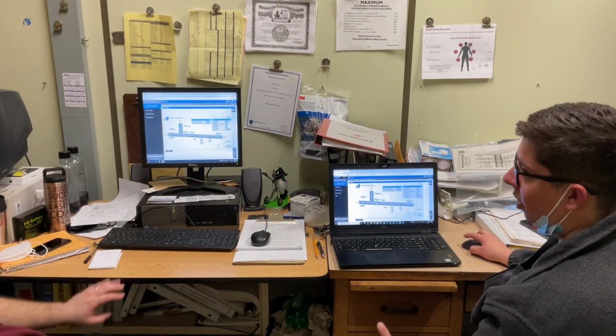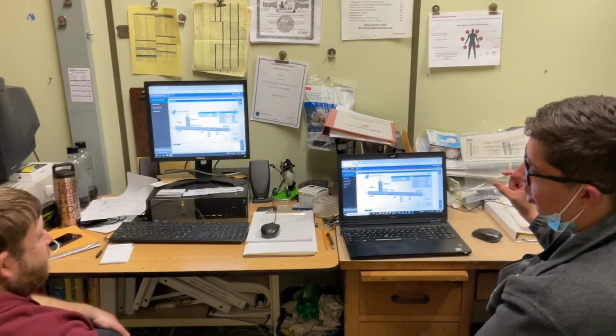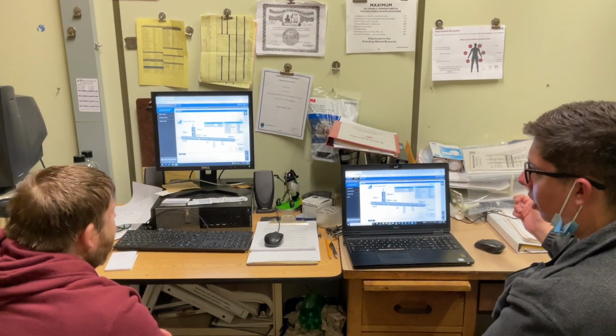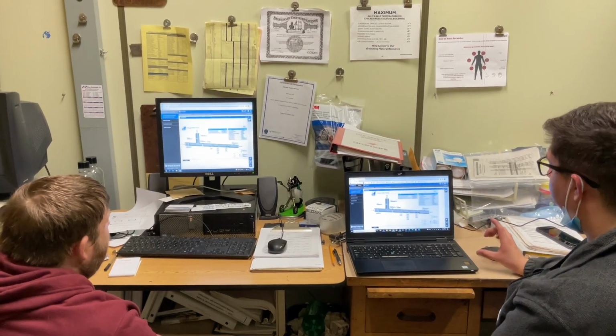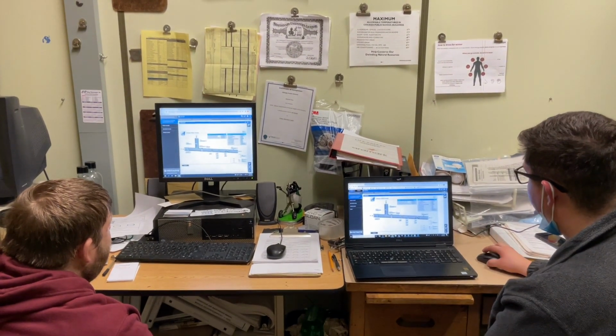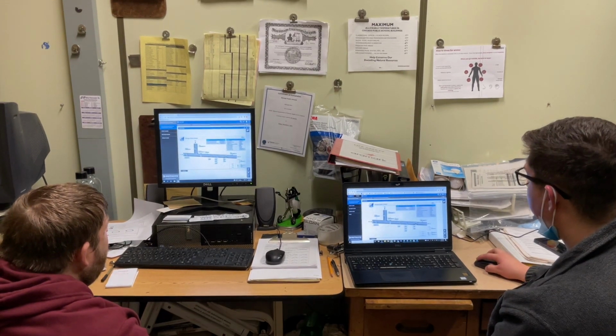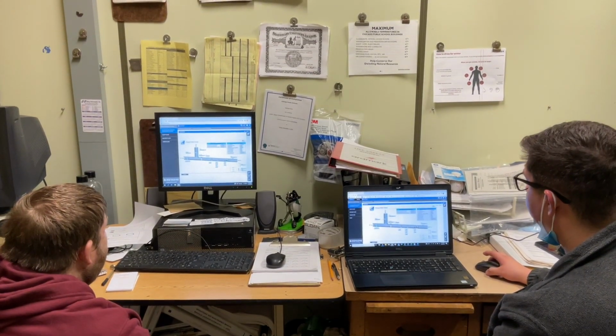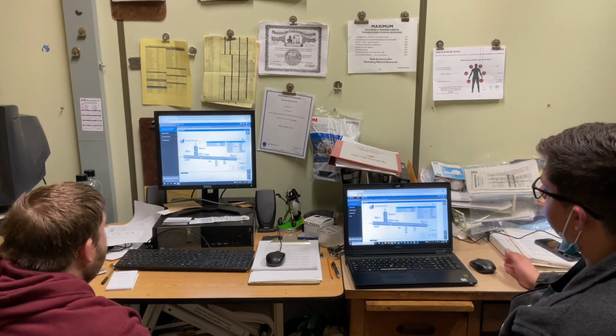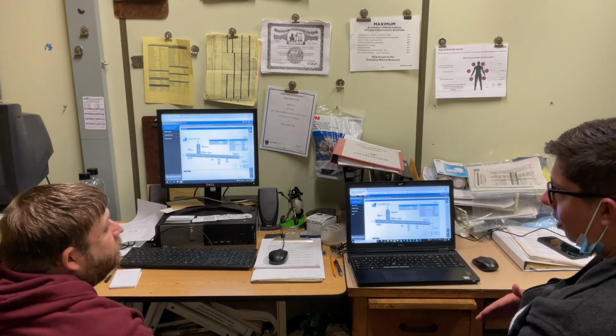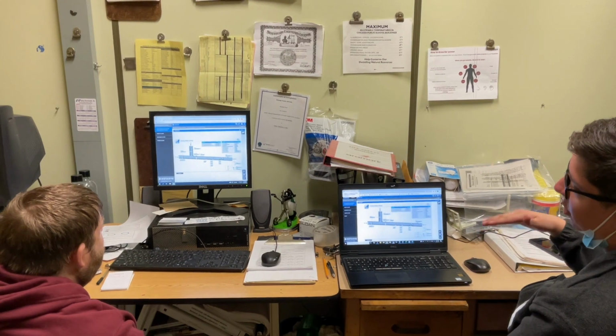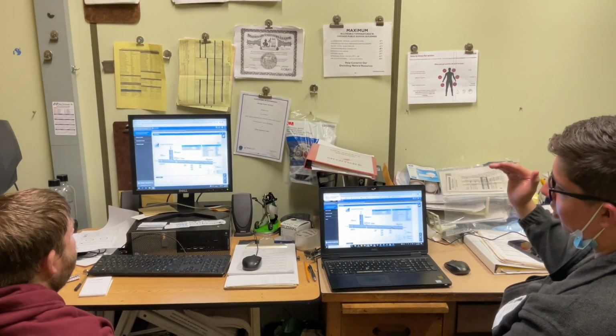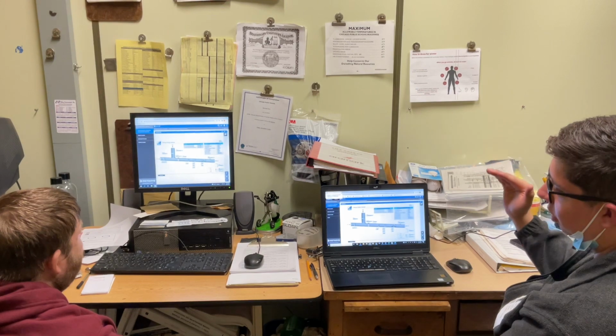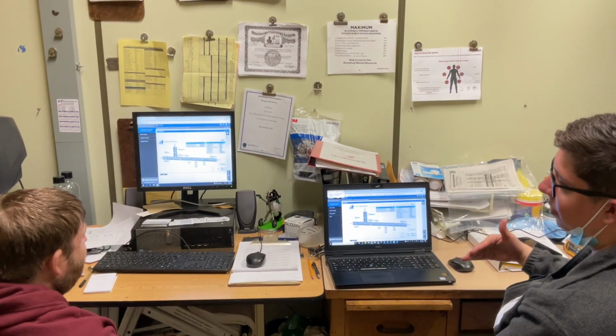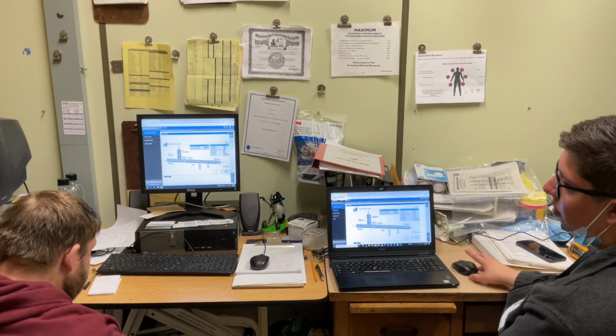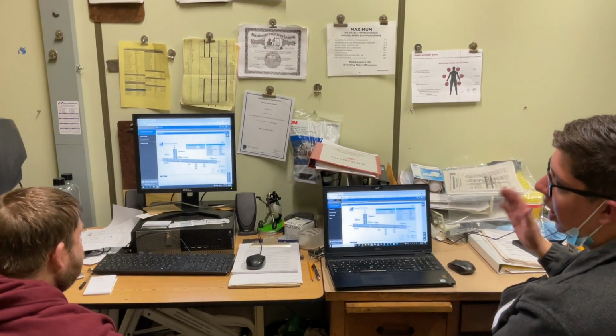Yeah. So you just set your set point. You're going to have plus or minus 2 degrees for your effective heating and cooling set points, and that's actually what it's controlling for. So at 76 on your set point, that makes your effective cooling set point 78, and your effective heating 74. So that means at a set point of 76, if the unit is heating, it's going to heat all the way up, and it won't switch back to cooling until it hits 78, and then it'll try to coast. As it starts cooling, it'll coast, and then if it gets below 74, it'll go back into heating. That just stops it from going hot, cold, hot, cold.